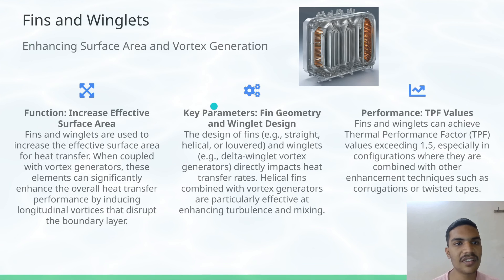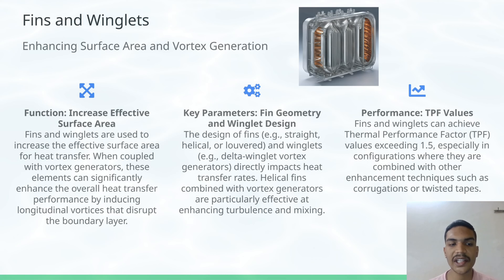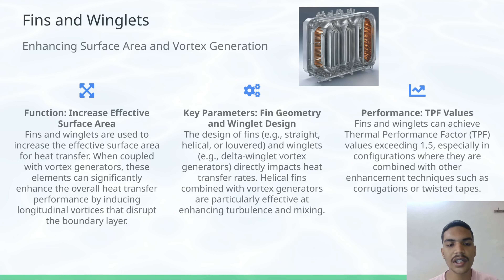Next comes Fins and Winglets. Fins and winglets are used to increase the effective surface area for heat transfer. When coupled with vortex generators, they significantly enhance overall heat transfer performance by inducing longitudinal vortices that increase turbulence and disrupt the boundary layer.